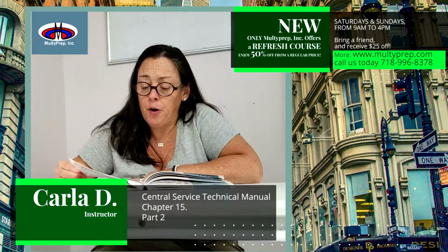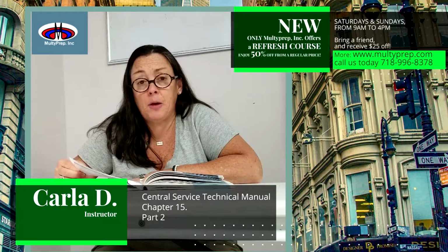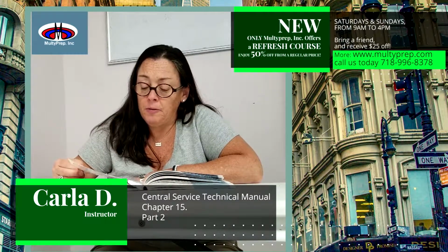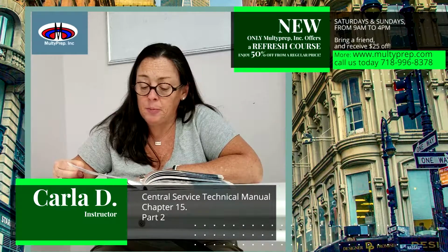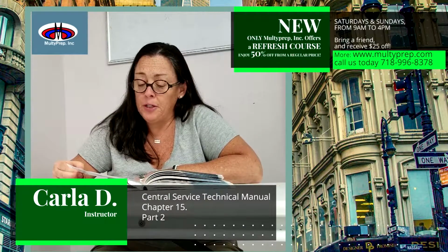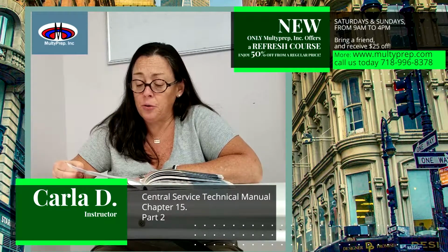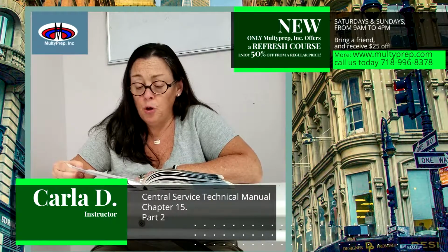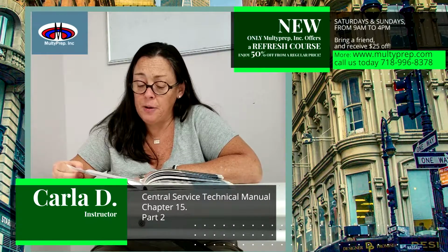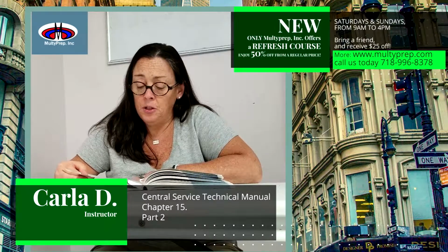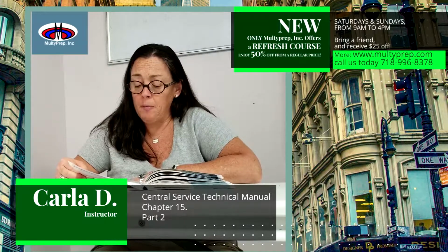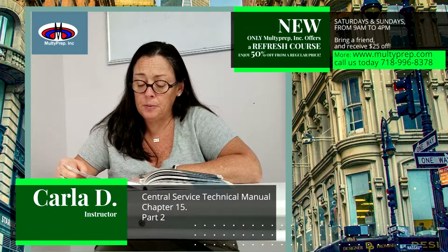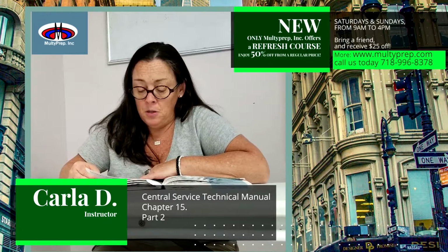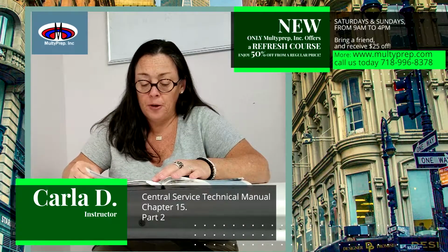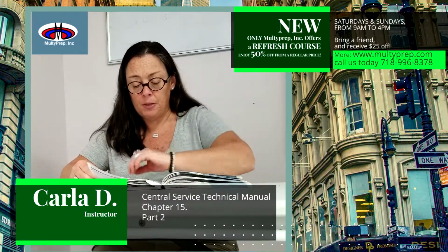Types of hydrogen peroxide gas plasma systems. There are several types of hydrogen peroxide gas plasma sterilizers available, ranging from compact systems with 28 to 38 minute processing times to large capacity systems with 75-minute cycle times. Different models have different cycle times, load capacities, and capabilities for processing instruments. See Figure 15.9 for an example of hydrogen peroxide gas plasma systems.